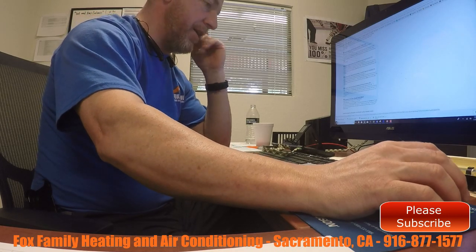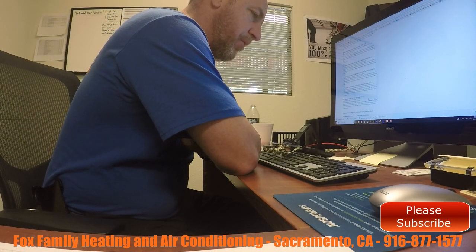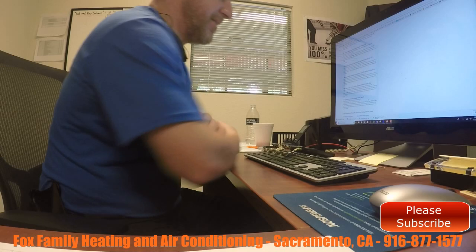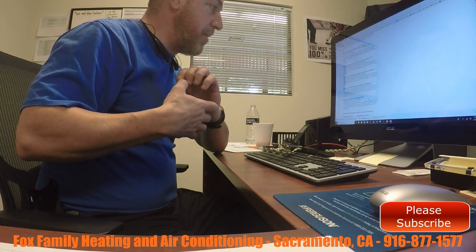Yeah, we can't just throw a board in there and test it, and then say, oh yeah, that works, so now you owe me $605. I mean, we've got to ask him, do you want to continue on with this diagnostic? Here's the thing. I've replaced the blower motor. Now the control board's acting up. The blower motor was running at this amp draw before, which is way above factory spec. So this is why we changed the blower motor, and that would let us test the system and see how it's running from there. Now the control board is saying it's got issues. Do you want us to continue diagnosing this, or do you want to keep making repairs on this?